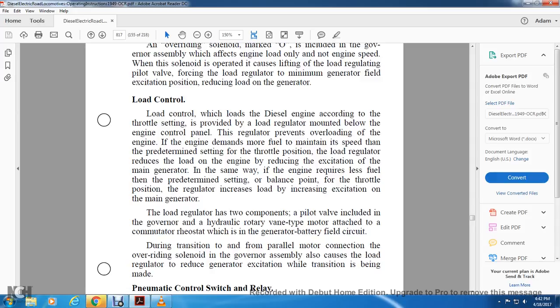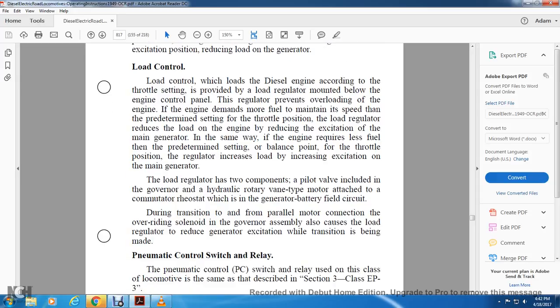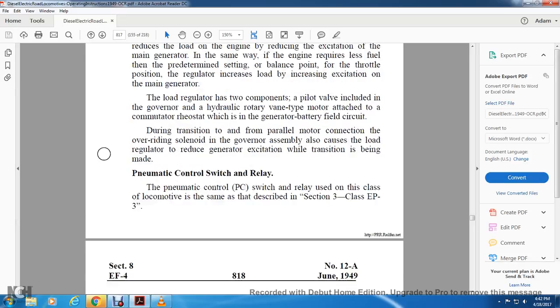The load regulator has 2 components: the pilot valve, included in a governor hydraulic rotary vane type, and the motor attached to the commutator rheostat, which is in the generator battery field circuit. During the transition to and from the parallel motor connection, the overriding solenoid in the governor assembly also operates the load regulator to reduce generator excitation when the transition is being made.